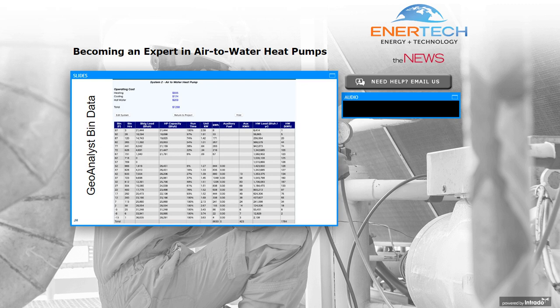This is a bin data-based software. So when you pick the city, it will automatically pull in the bin data. The bin data are 5-degree temperature bins on outdoor air temperature so that we know how many hours per year we are at each of those bins. So this happens to be Syracuse, I believe, at 22 degrees outside in that bin anyway. We have about 400 hours per year. So based upon the location, you can really dial in exactly how this thing's going to perform.